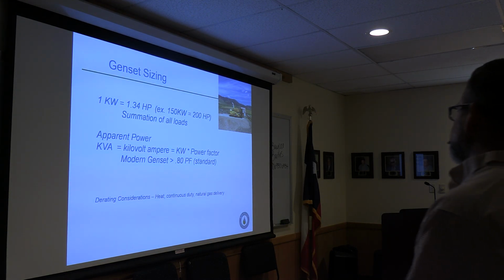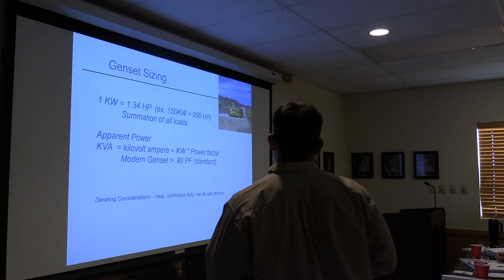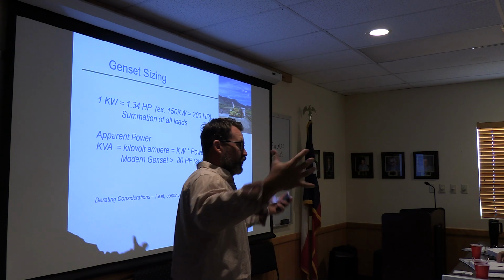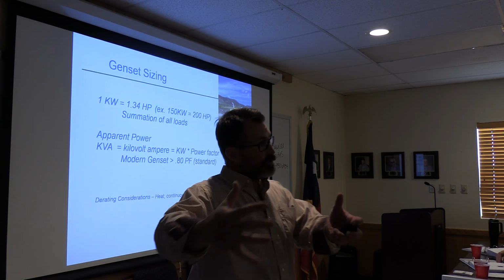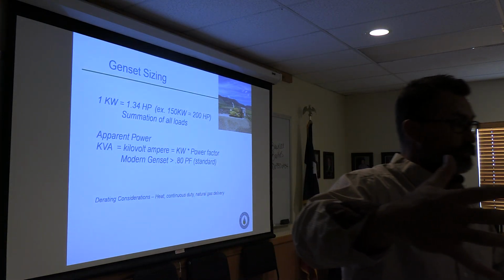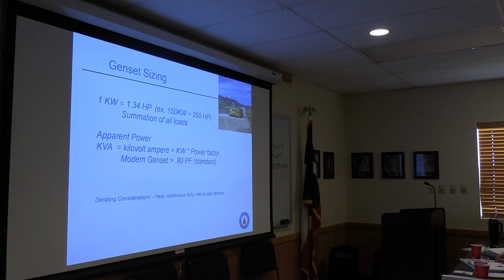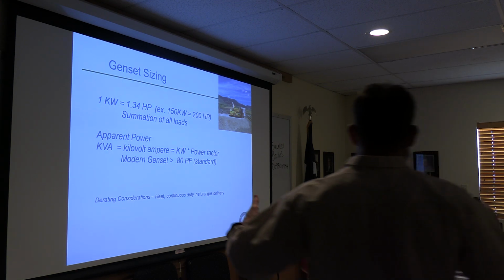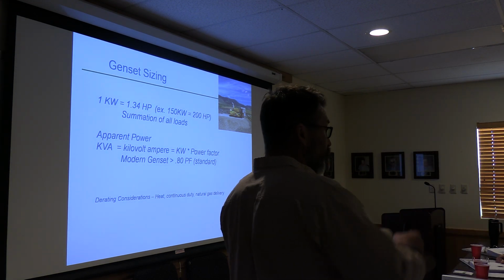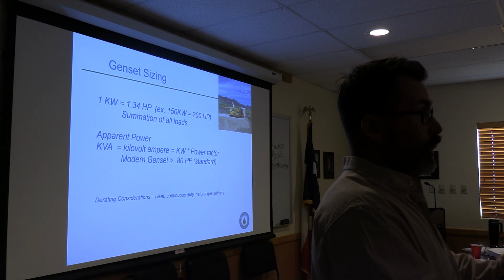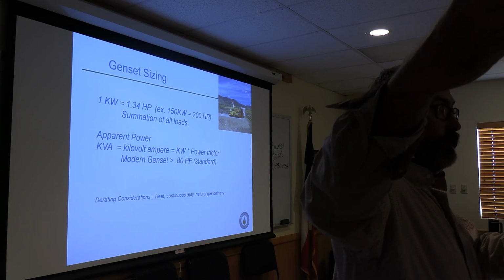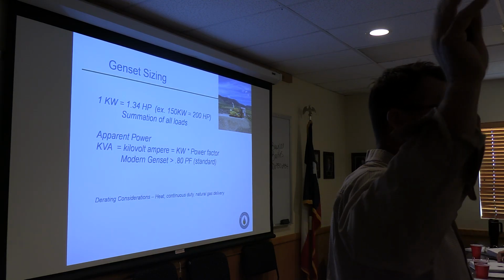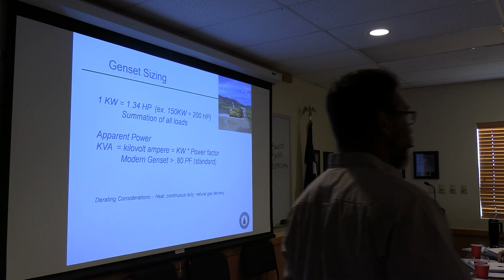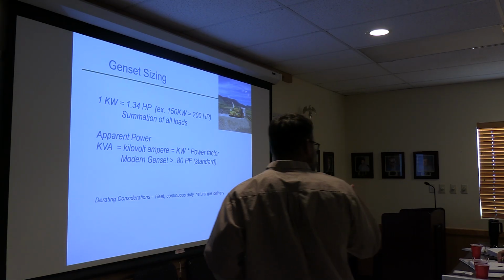So sizing this gen set is going to be critical. Remember, you become a utility now, so you need to have a sense of what all of your loads are. Then you need to build your infrastructure out to match those electrical loads. It's not complicated, but you can't really guess on this, because with a gen set application you're going to start fine tuning where you'll end up with a load, and you don't have the abundance of the grid that would be carrying all your neighbors' loads to help you. So you have to start paying attention to things like, what's my line sizing?